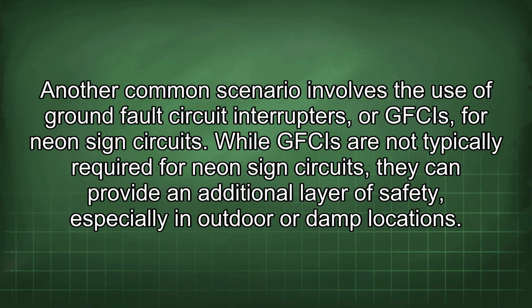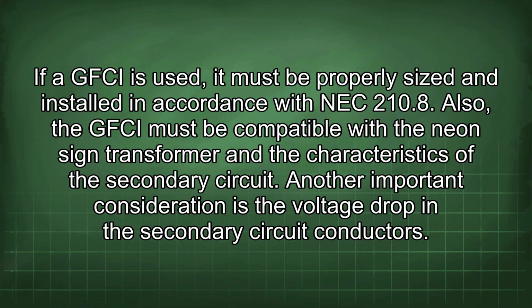Another common scenario involves the use of ground fault circuit interrupters, or GFCIs, for neon sign circuits. While GFCIs are not typically required for neon sign circuits, they can provide an additional layer of safety, especially in outdoor or damp locations. If a GFCI is used, it must be properly sized and installed in accordance with NEC 210.8. Also, the GFCI must be compatible with the neon sign transformer and the characteristics of the secondary circuit.